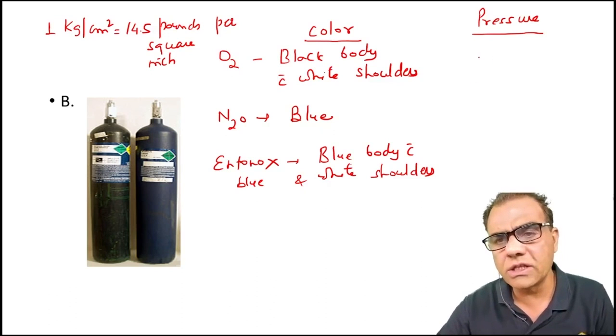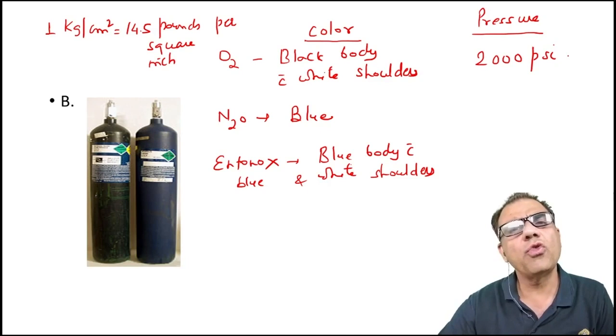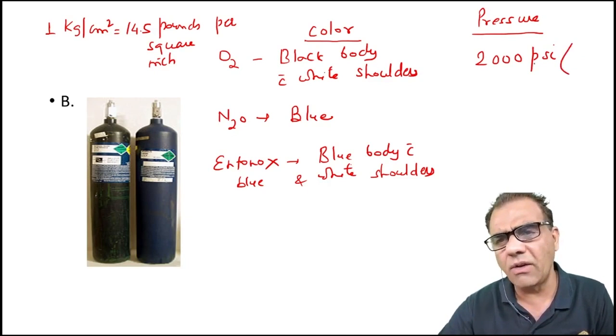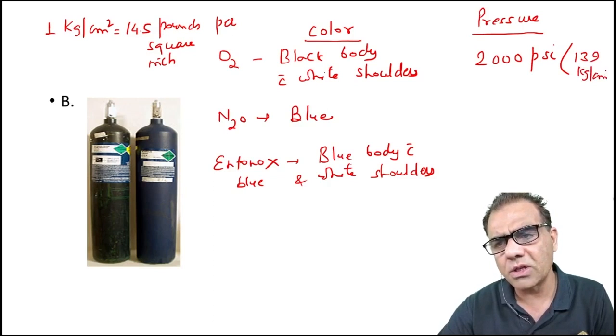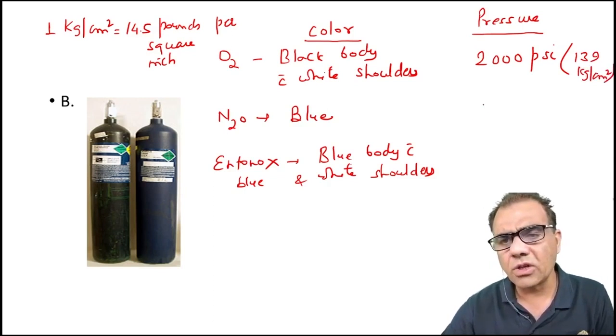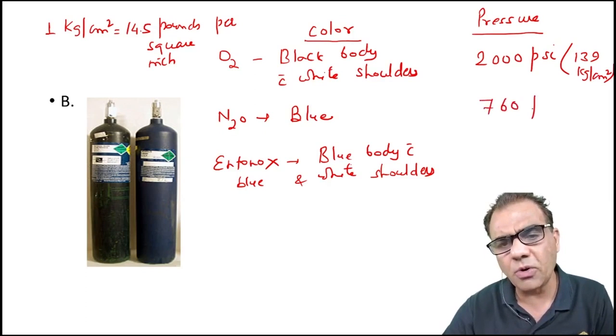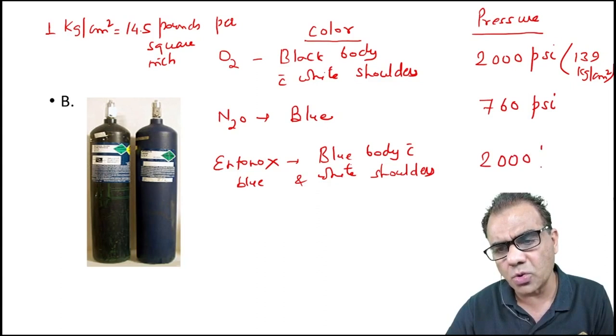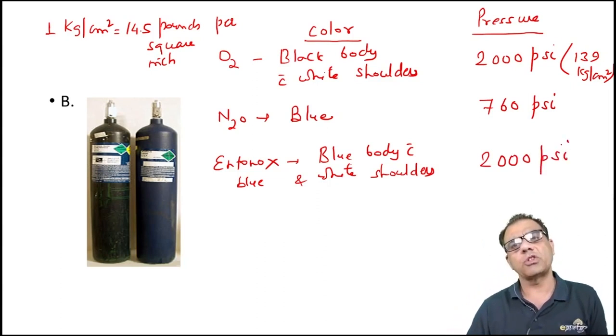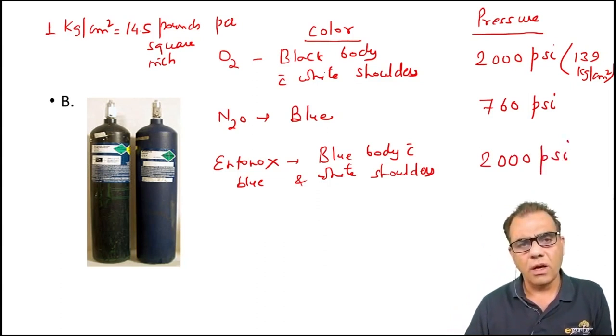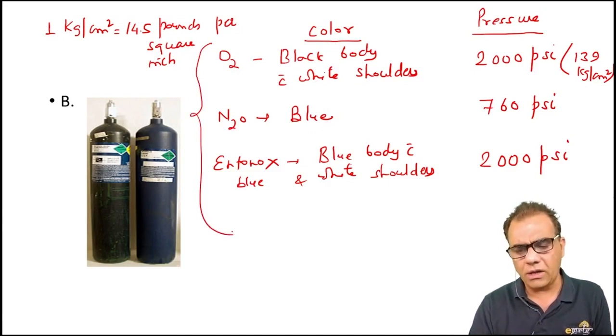So in a full oxygen cylinder, the pressure is 2000 pounds per square inch, which if you convert into kilogram per centimeter square, divided by 14.5, it will come around say 139 or 140 kilogram per centimeter square. Nitrous oxide, the pressure is 760 pounds per square inch, and Entonox, already we have discussed, the pressure is 2000 psi, that is the pressure of oxygen. Now with this background, we'll again have a relook at this question.